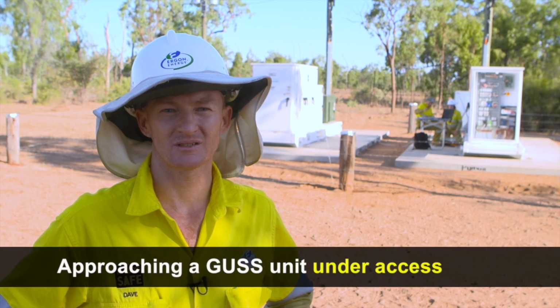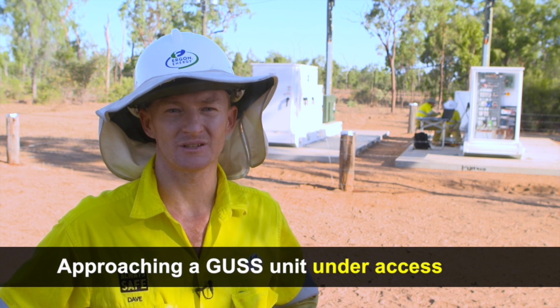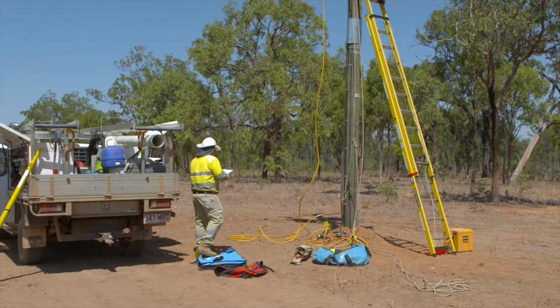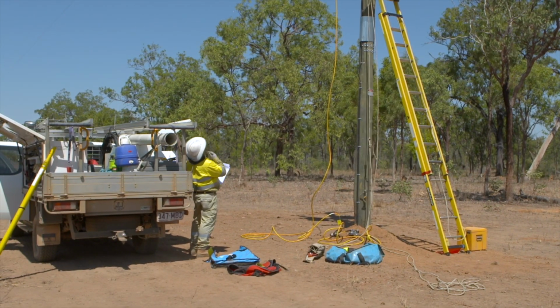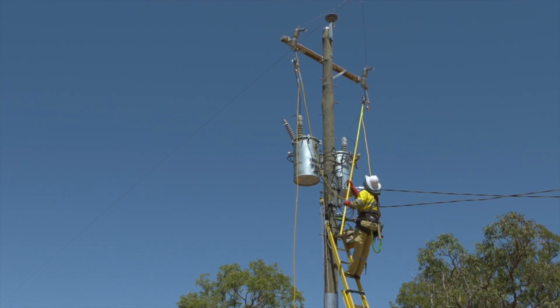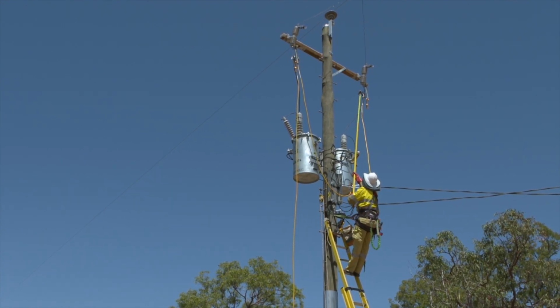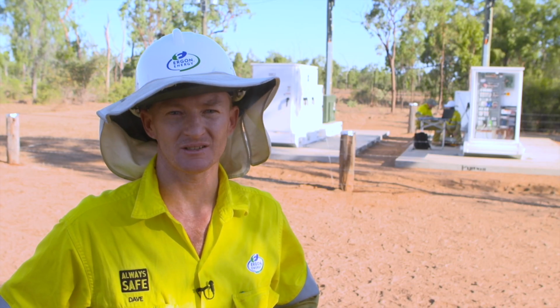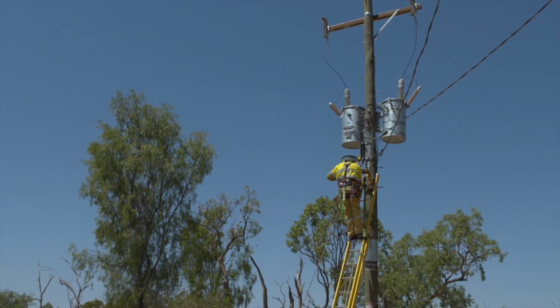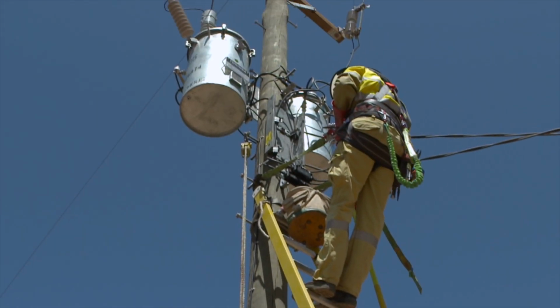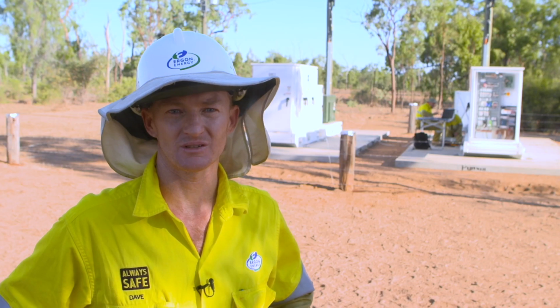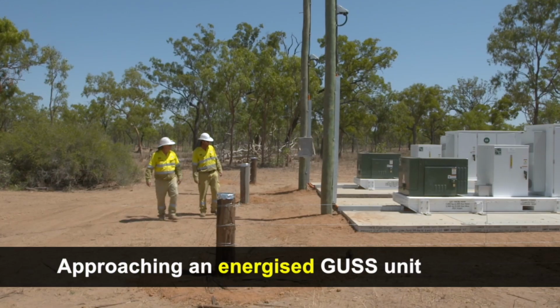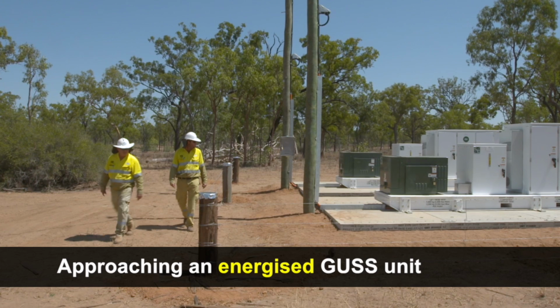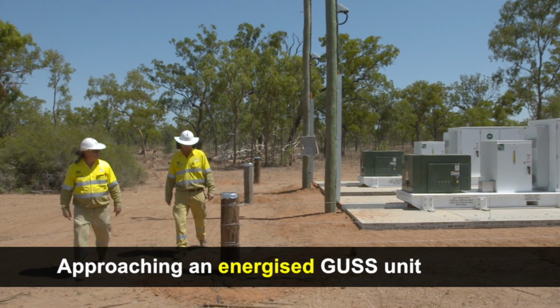In most situations, LV isolation at the pole and on the DC side of the GUSS unit is adequate for access. If the GUSS unit is isolated as part of a switching sheet, then access requirements will be in accordance with our P53 processes. If you are accessing the overhead distribution network, that is the SWER conductors, once again follow the normal P53 processes. You could be asked to approach an energised GUSS unit for fault finding, line patrol as a result of a loss of supply. Keep clear of any defects or suspected defects until proven safe to touch.